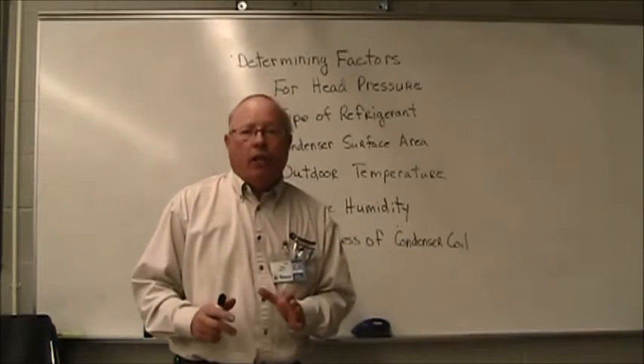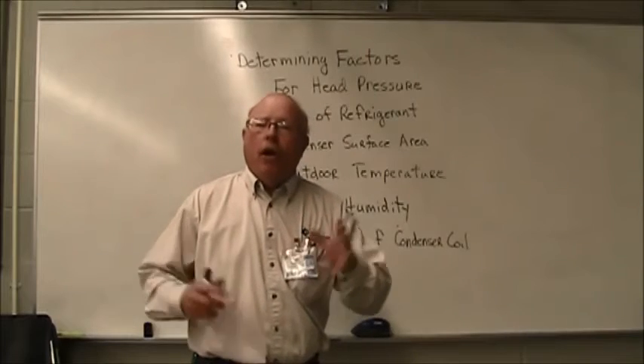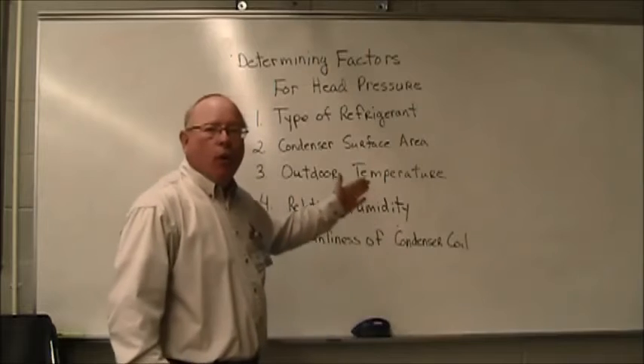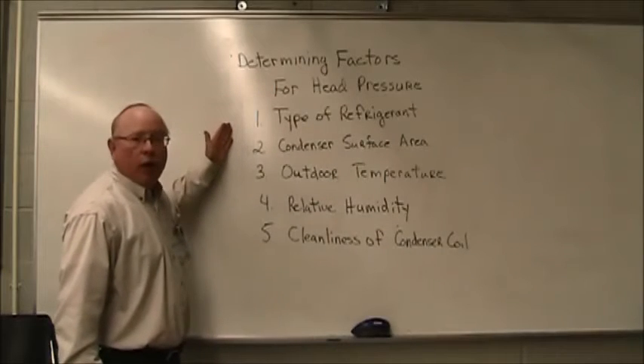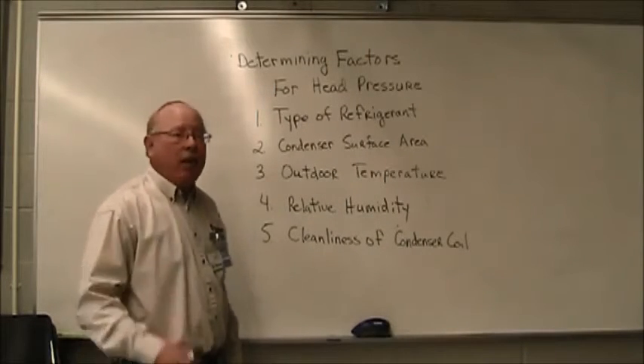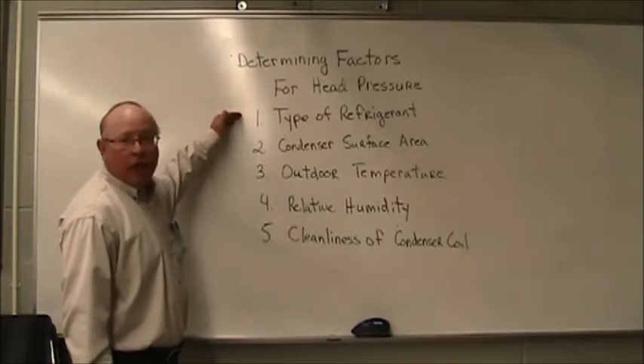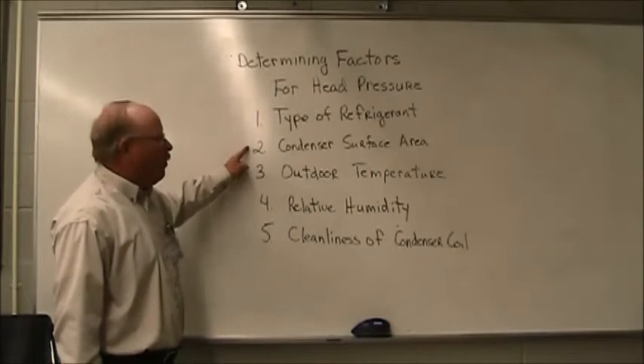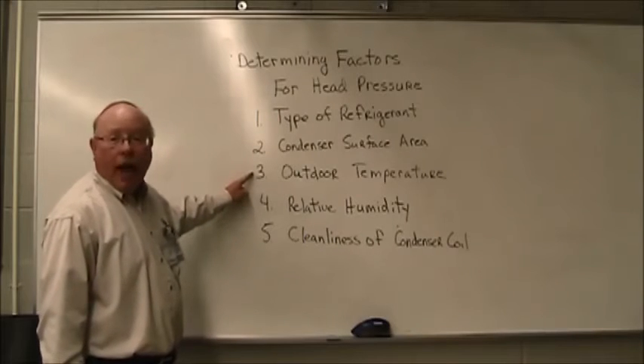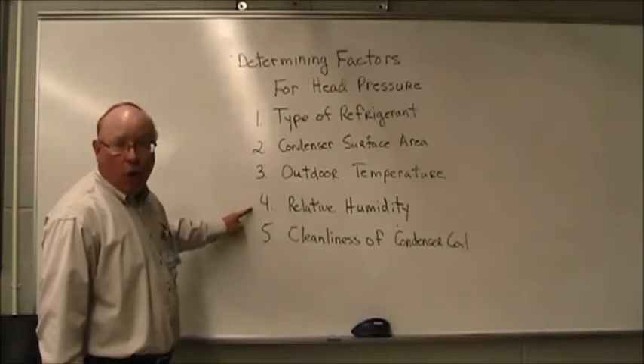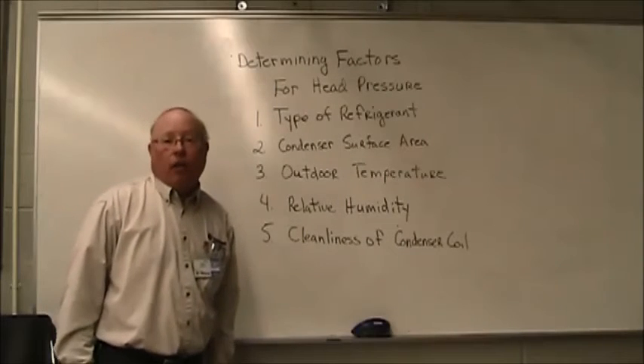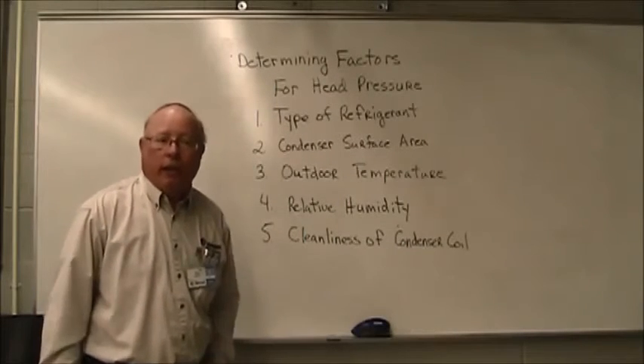In having head pressure, what's going to determine what the head pressure should be? I've listed on the board here five things that are going to determine what the head pressure should be in any unit. First, the type of refrigerant. Second, the condenser surface area. Number three, the outdoor temperature. Number four, the relative humidity. And number five, how clean is the coil, or the coil cleanliness.